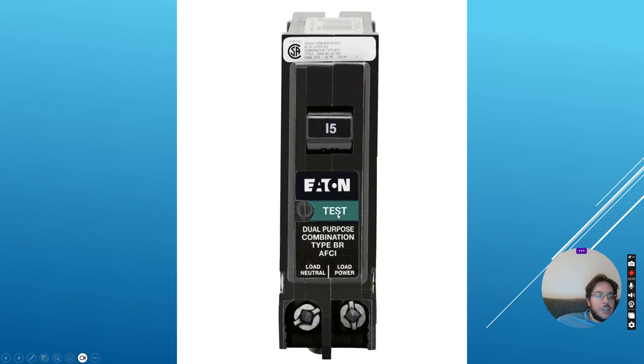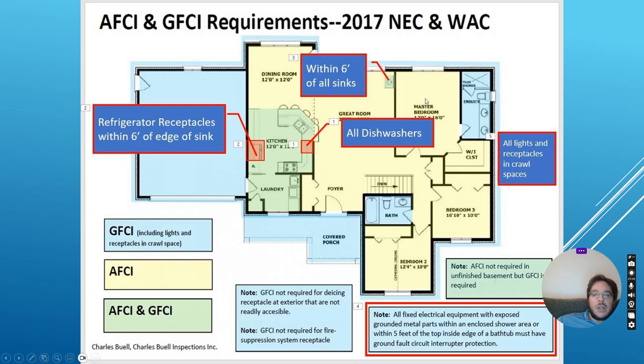Now, I mentioned this earlier, but what has been mandated is the AFCI breakers. An AFCI breaker prevents fires that are caused by arc flashes, and you want to get one that says combination type, because a combination type breaker protects against arc flashes on series and parallel circuits. They're more expensive than regular breakers. In Canada these are like $90, and in the US they're much cheaper, but they're still way more expensive than a standard breaker. And now Canada and the US require them.